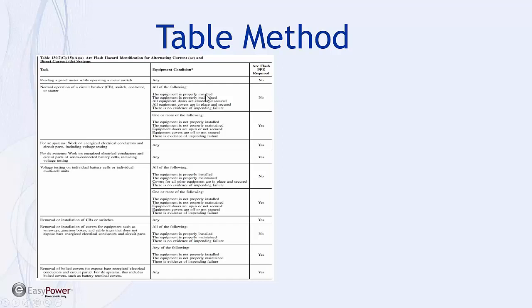Is the equipment properly installed? Is the equipment properly maintained? Are all the equipment doors closed and secured? Are all the covers in place and secured? And a big one: is there no evidence of impending failure? If all those can be answered affirmatively, and all we're doing is operating a circuit breaker, contactor, or motor starter, then it's not required to put on PPE.